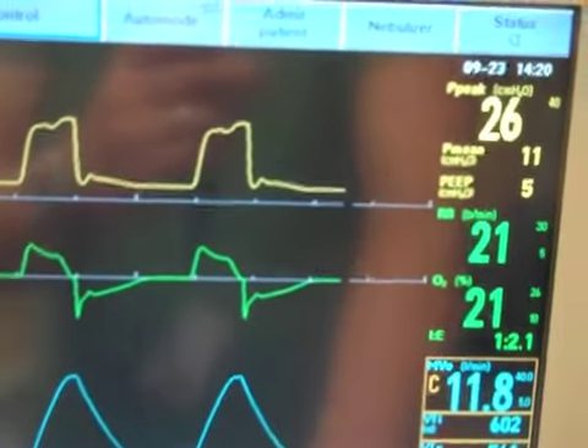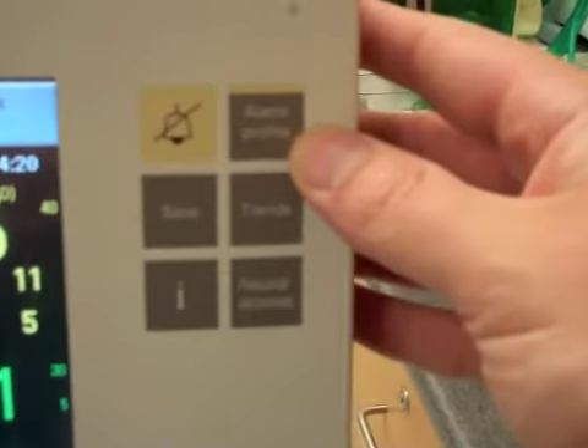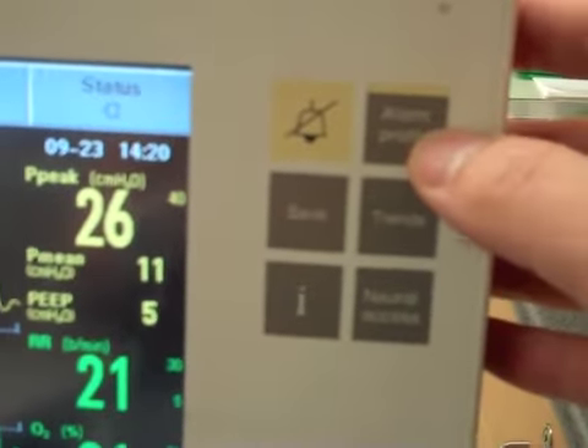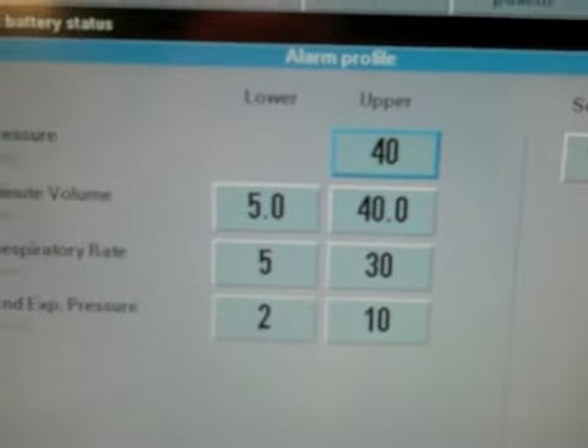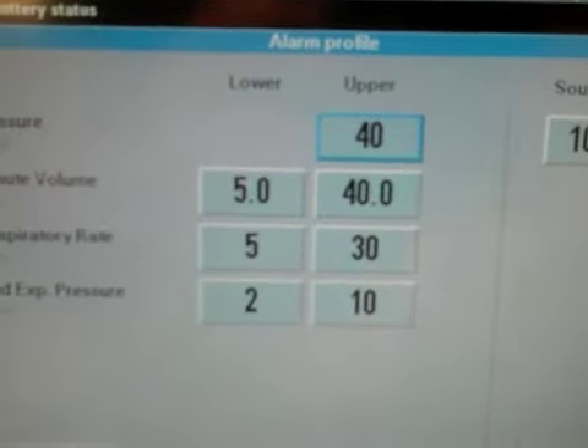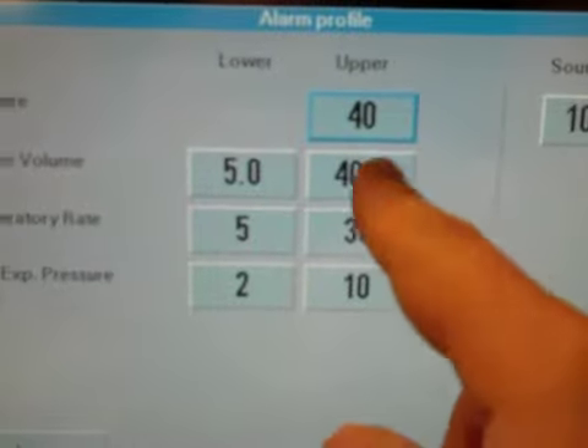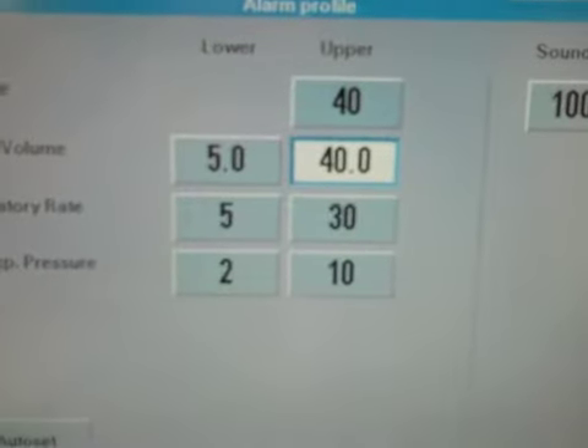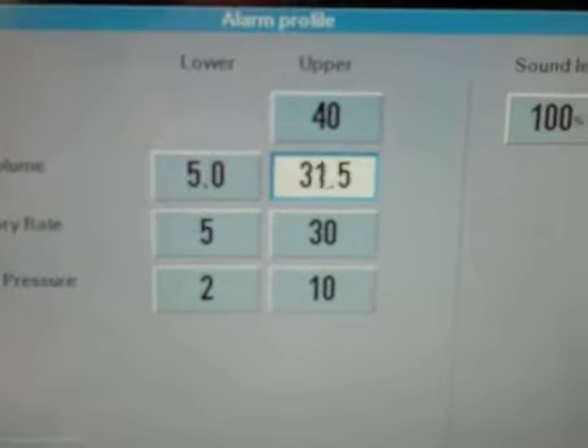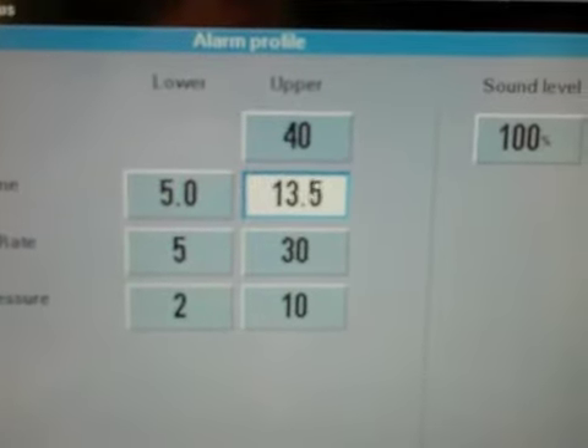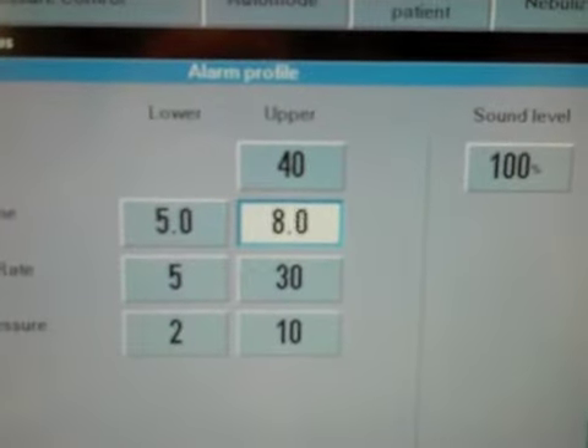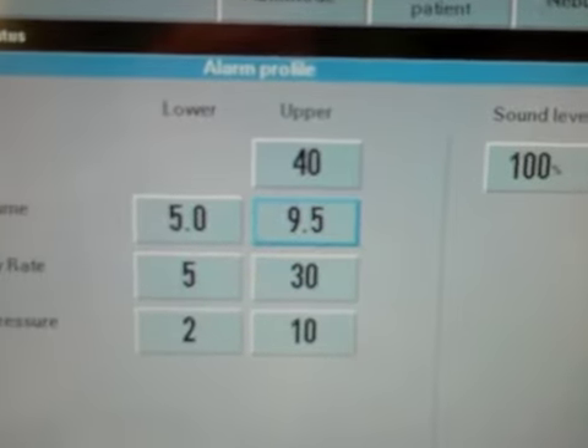close that out, and we're good to go. Your alarm profiles, something that we didn't do and we should have done before we started ventilating. Up in the right corner, if you select alarms, you can select your different profiles. So we have pressure, minute volume, respiratory rate, and then expiratory pressure. So for instance, a minute volume of 40 would be a little excessive, so if we came down to something more appropriate prior to our ventilation strategy, simply put that in, push the button again, accept that, and you're off to the races.